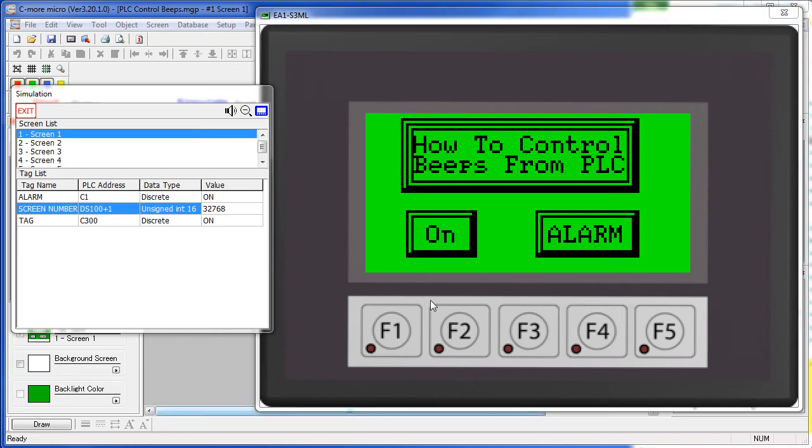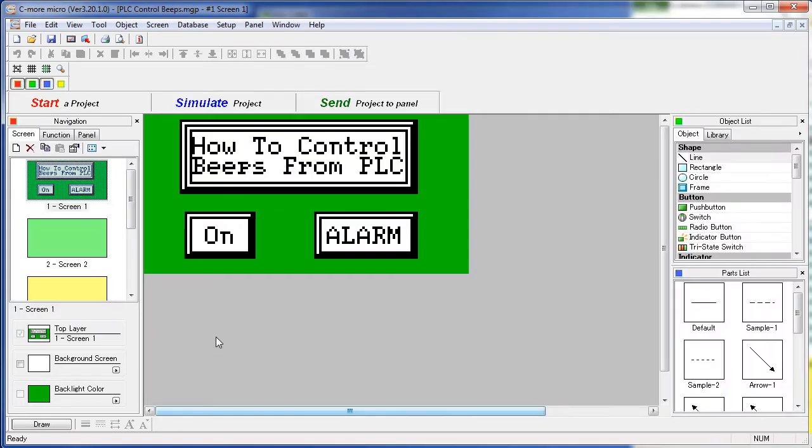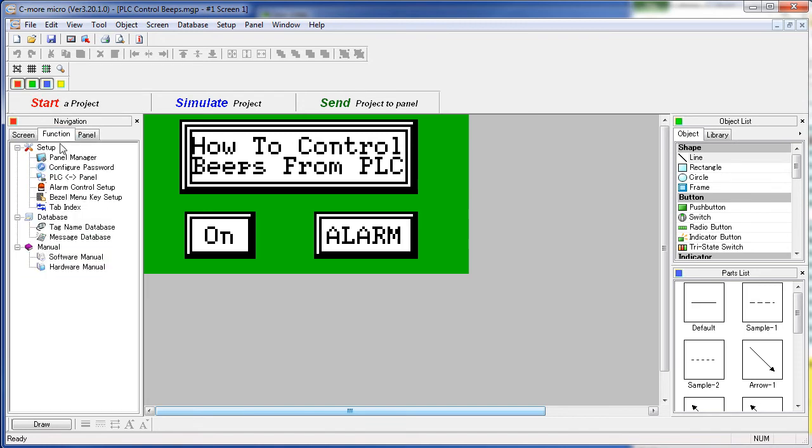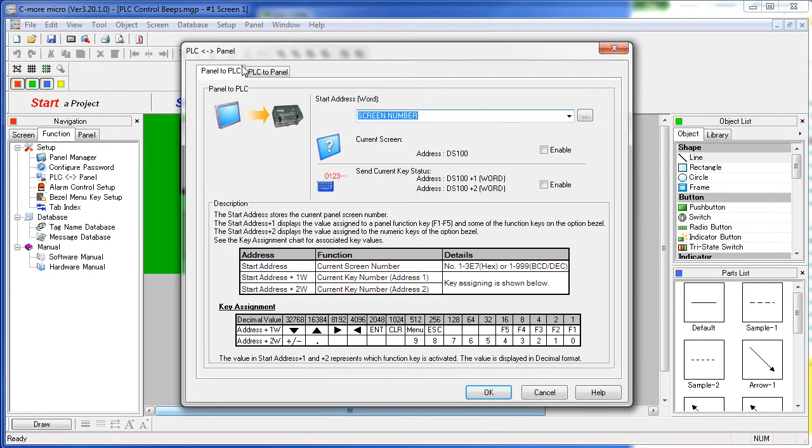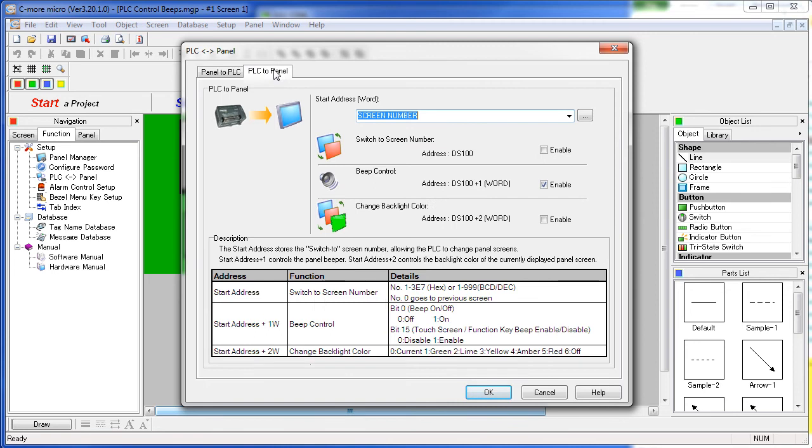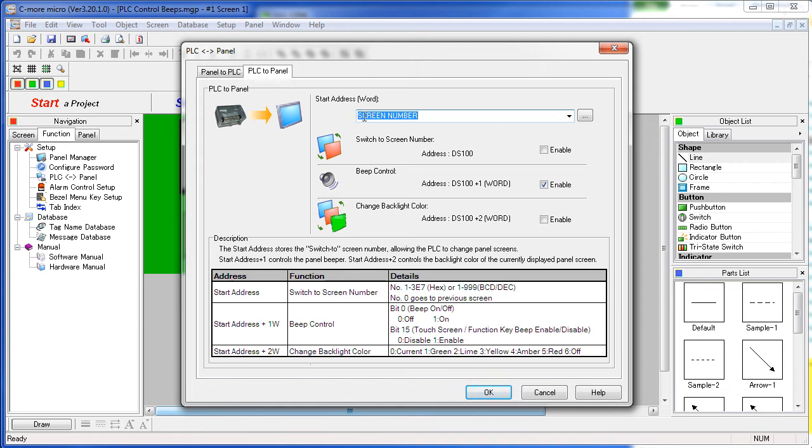Setting all of this up is easy. Just go to the Navigation Windows Function tab – PLC to Panel or the Setup menu – PLC to Panel. Go to the PLC to Panel tab – put a tag in here for the C-more Micro to monitor for this screen number. The C-more Micro will watch that tag and use it to change screen numbers if that feature is enabled. We don't have it enabled right now.